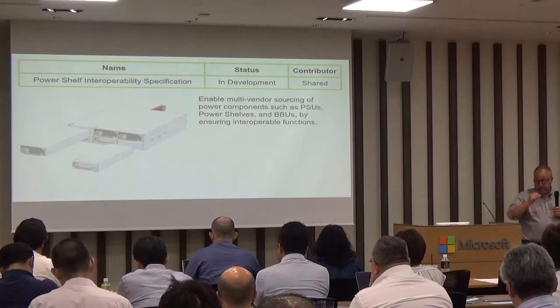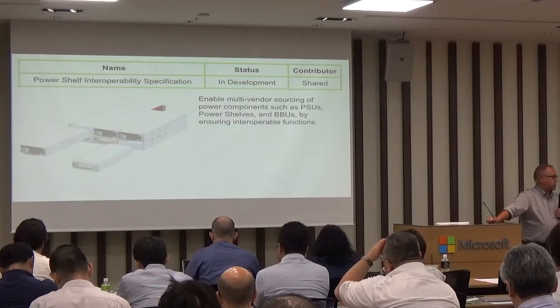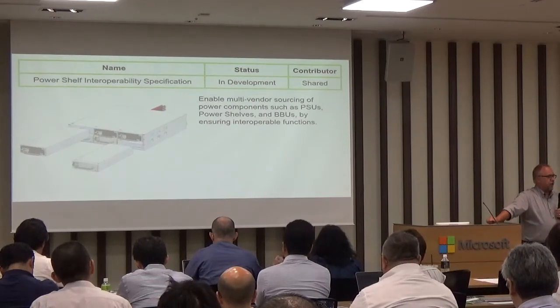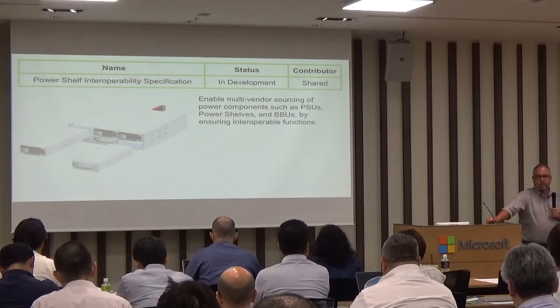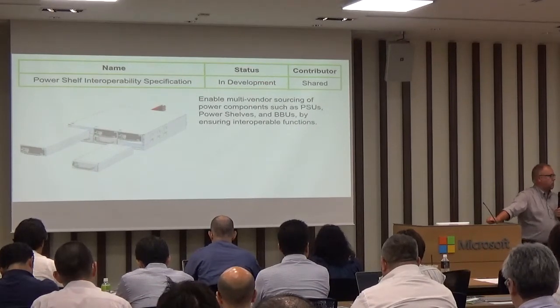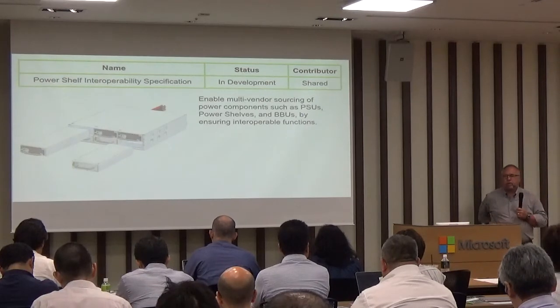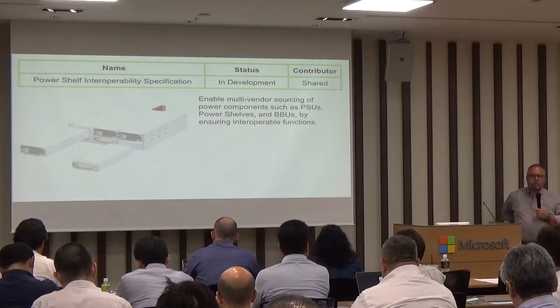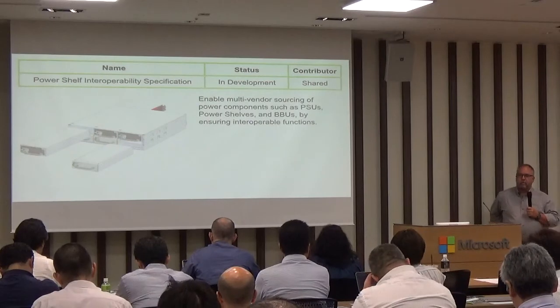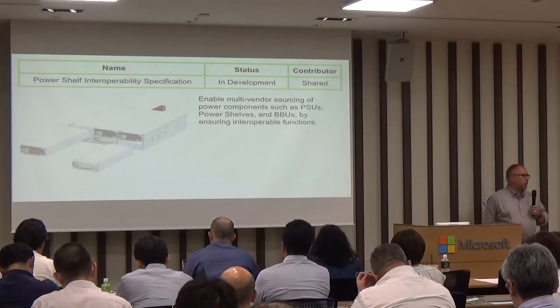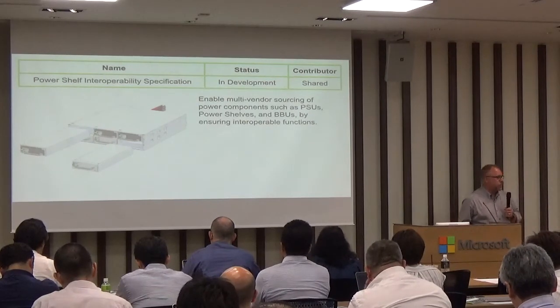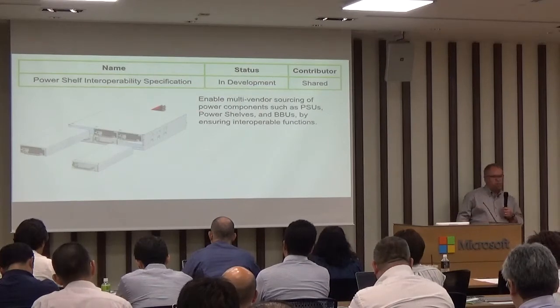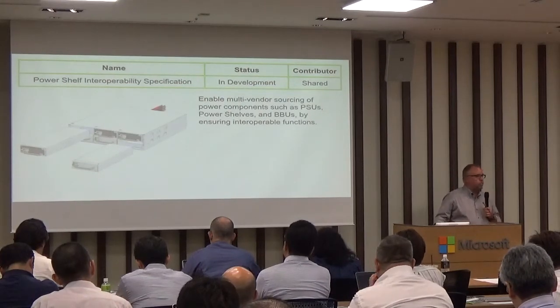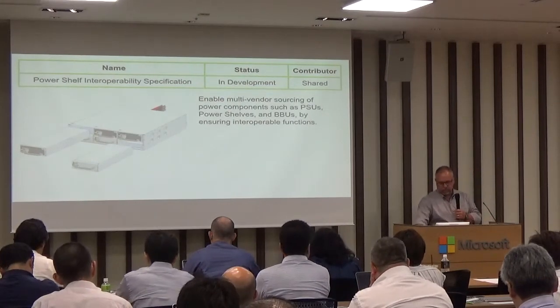This also allows you to interchange these with modules that have battery backup or lithium batteries in them, providing UPS functionality in the rack. So rather than having a separate UPS room, we now have the capability to have UPS functionality directly in the rack, giving us flexibility through an interoperable power shelf specification.